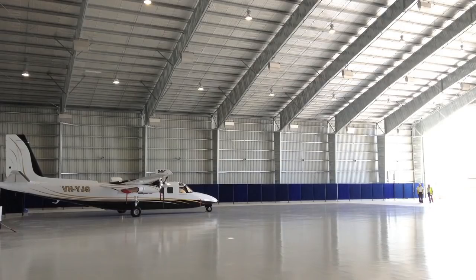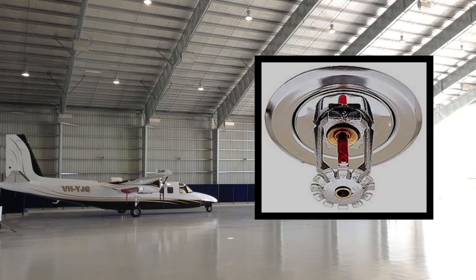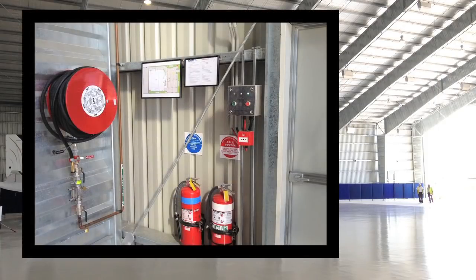To protect against internal fire spread, the adjoining pump house and offices are sprinklered. This has the added advantage of eliminating the need for costly fire-rated walls and doors. To attack small fires, fire extinguishers and fire hose reels are placed near exits.